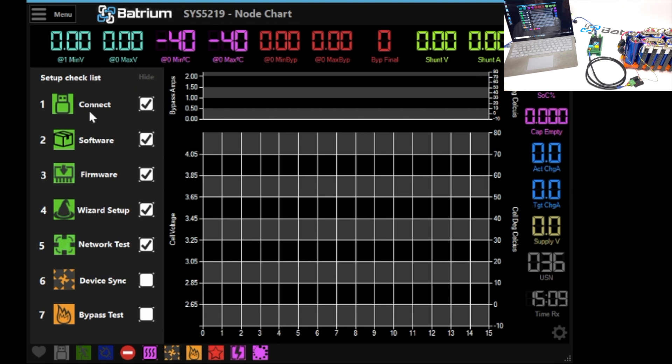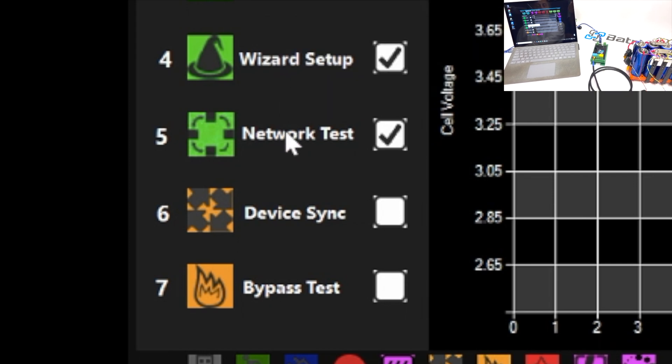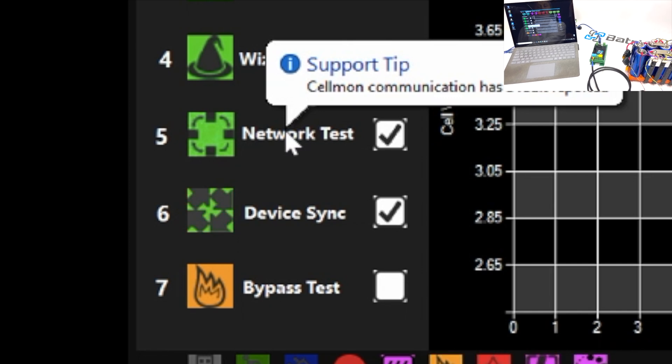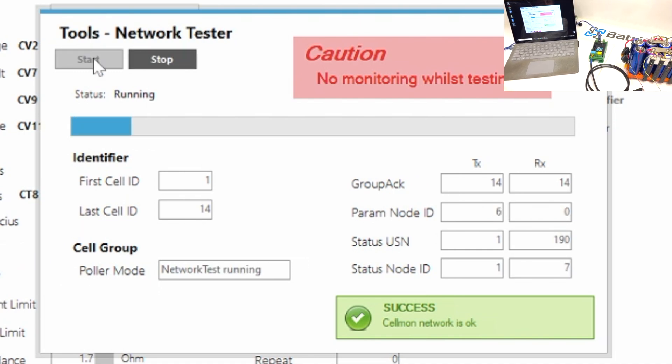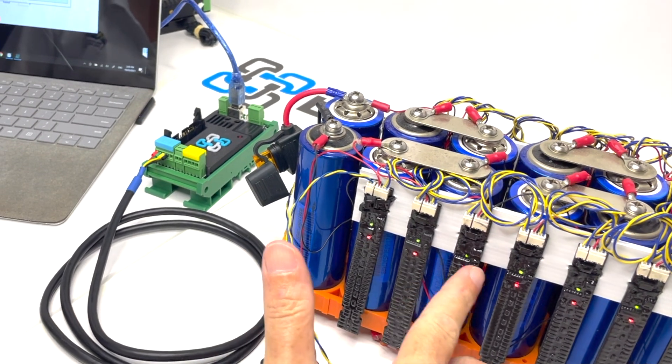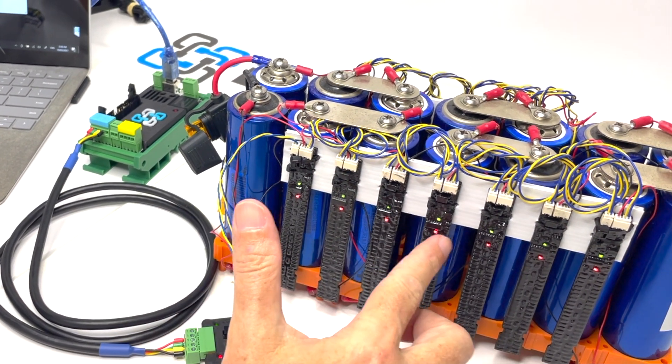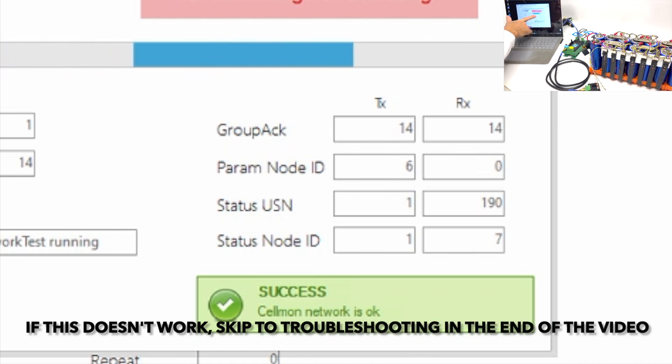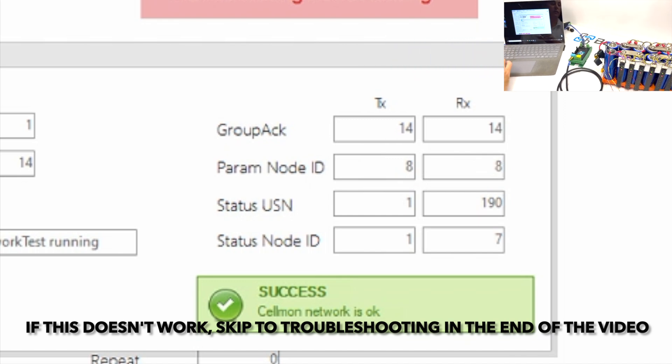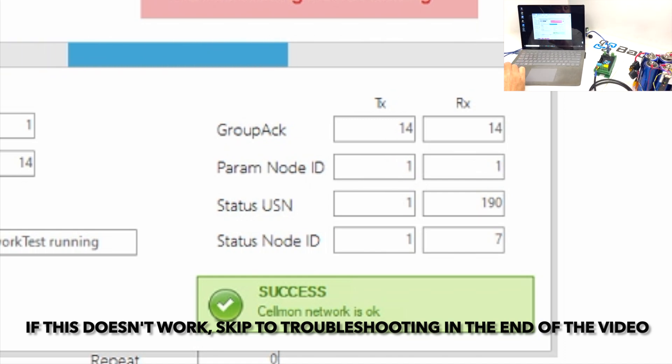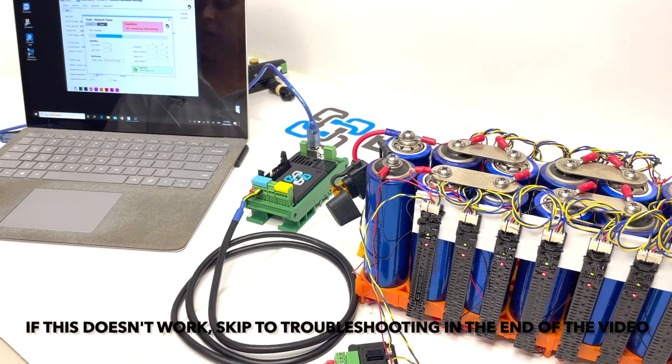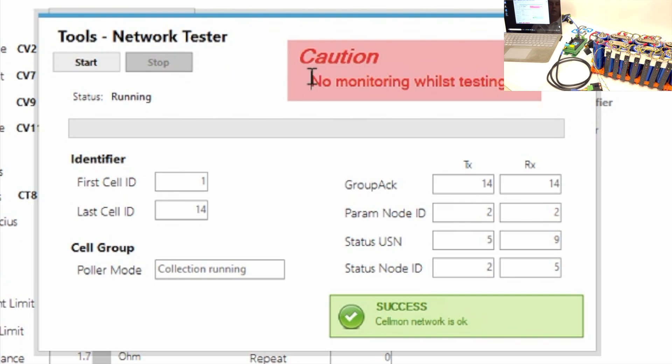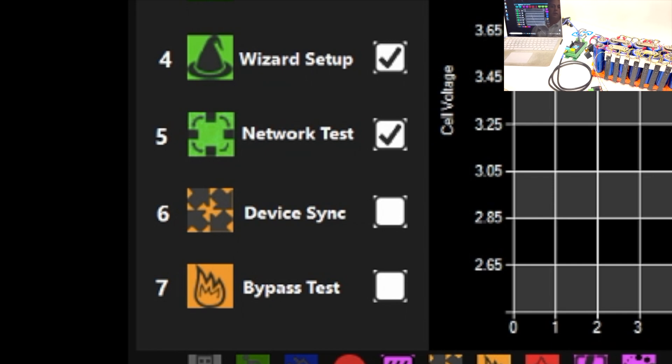All right let's now move to the next step. Now if there was any issues it would actually need some network testing but we'll do it anyway even though it's detected that it's working. So we go to network test and we start the network tester. Now you would ask what is this actually doing? Now if you actually come across here to the LongMons what you'll see here is there is a green light on and a red light and it's across every single LongMon and what we're able to do is determine that each one of them is communicating. And on the software what we can see is that there is 14 cells that we're expecting to see from and 14 cells are being acknowledged. So that's the perfect outcome for us because we're able to see that the number of cells do match the number of cells that are configured. With the lights on we know that we've got working we've got a green light to say the network is okay so we can proceed on. So we will go back over here and stop the network test and most importantly when we go back to the menu we can see that it's saying that the network test is complete.